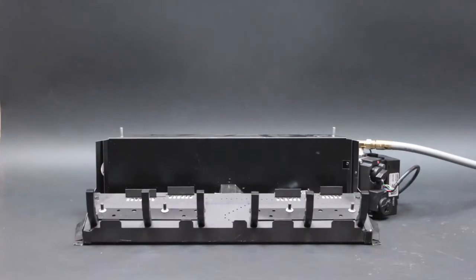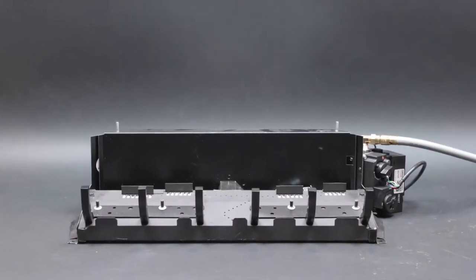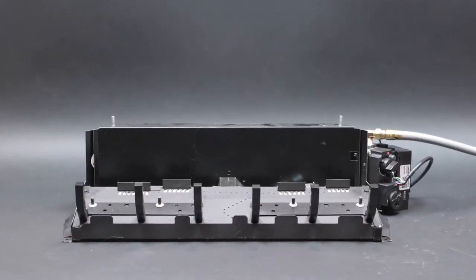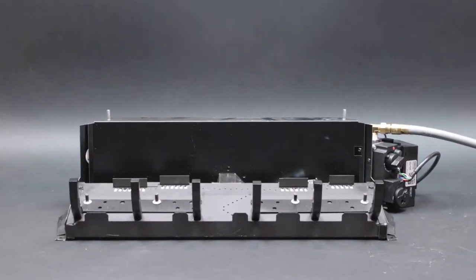Today, we will demonstrate how to test the thermocouple voltage output of the Maxitrol GV60 control system. You would conduct this test in cases where the pilot lights but the burner does not.